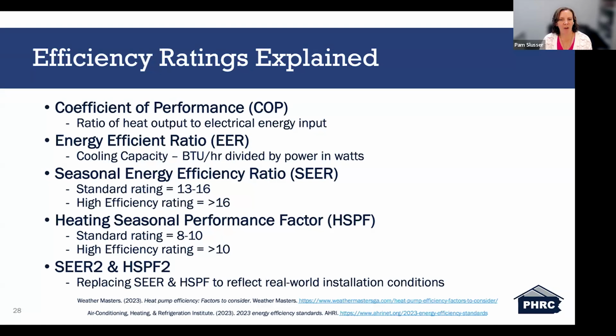And then what's new is the SEER2 and the HSPF2. Beginning in 2023, the Department of Energy introduced SEER2 and HSPF2 to better reflect real world performance, accounting for external static pressure and the system installation variables. These updated ratings require more rigorous testing, meaning the numbers may appear lower, but the systems themselves are not less efficient. So think of SEER2 and HSPF2 as more accurate versions of the original ratings. They help us better understand how systems will actually perform in homes, not just in the lab. Right now we're still in a transition period, so you may still see equipment listed with just SEER and HSPF, but SEER2 and HSPF2 are becoming the new norm. So you'll be seeing them a lot more.